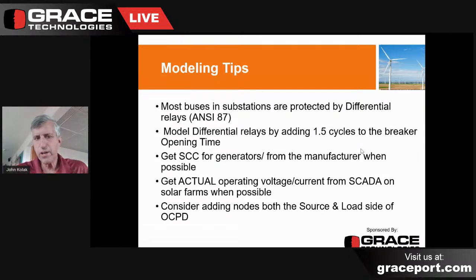I already mentioned this earlier. Get your short circuit calculations from the manufacturer when you can, and get actual operating voltage and current from SCADA when you have the opportunity. Once again, combiner boxes, for example, the actual amount you have in there may be considerably different than if you just did a straight calculation. So take that into consideration as well. And then consider putting nodes, calculation nodes, on both the source and the load side of your overcurrent devices.